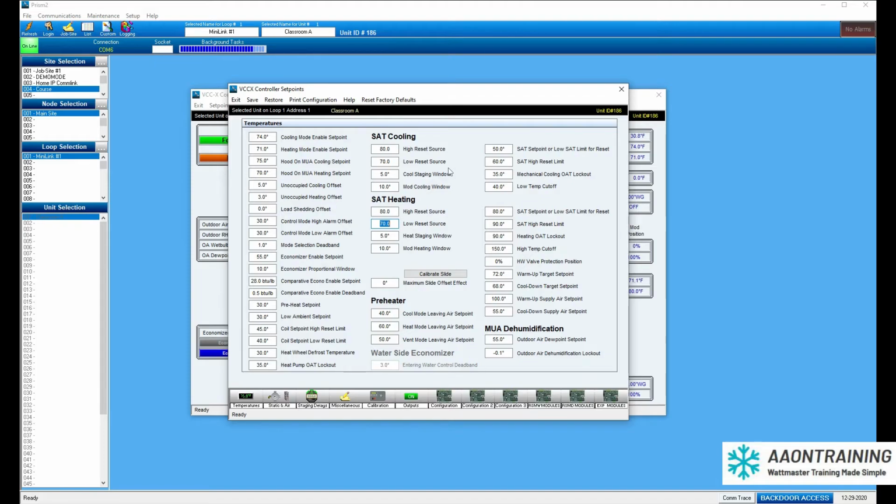So just keep in mind that if the space needs a reset and it needs to be very, very finely tuned control, such as lab applications or things like that, then that's great, and it has a functionality to do that, and it works very, very well. On the other hand, if it is let's say building pressurization, you might need it, you might not need it, but just make sure that if you do start putting in some of the more fancy and robust settings in here, it's able to be actually managed by the technicians who are running the facility.